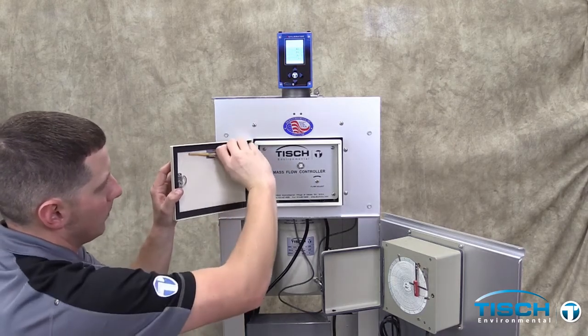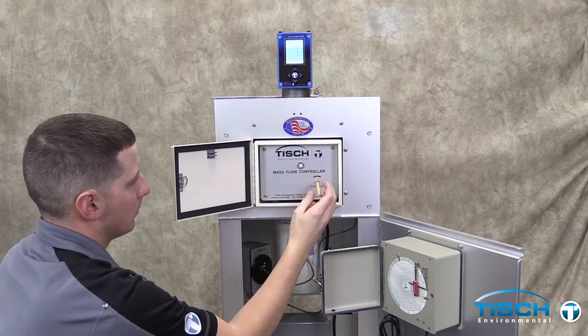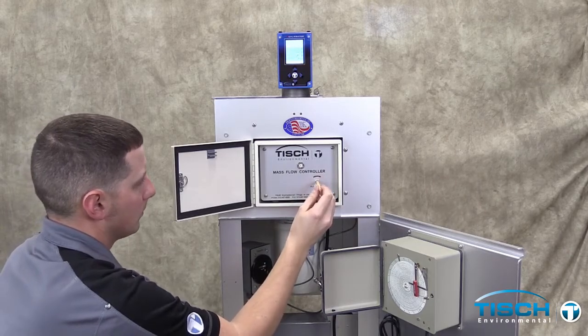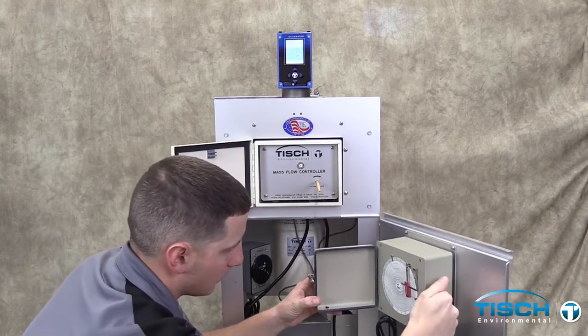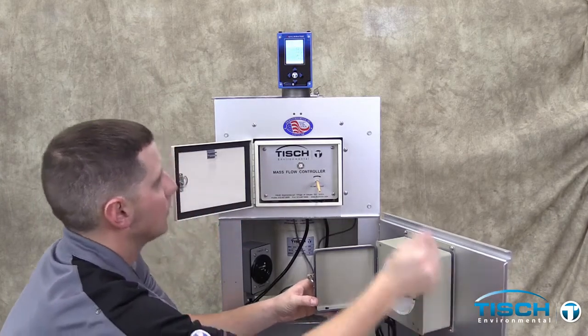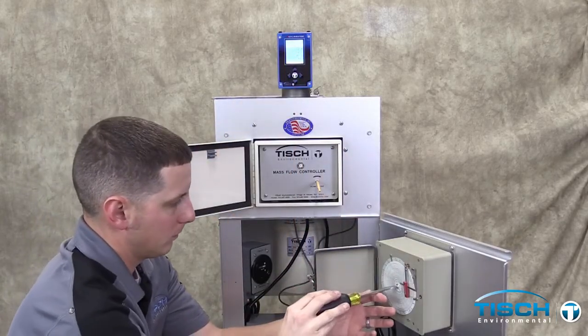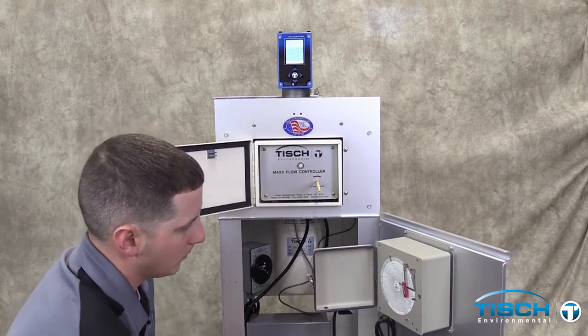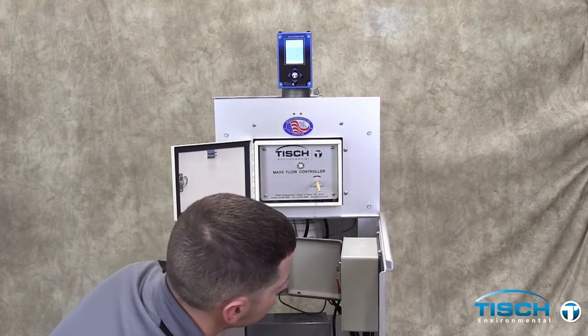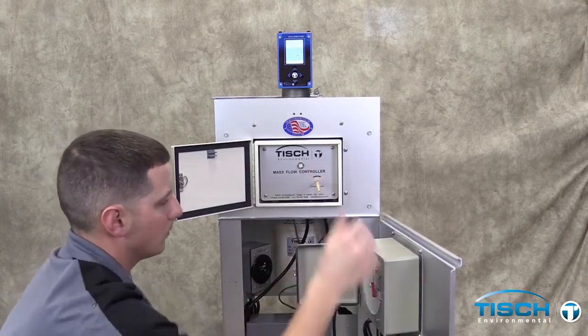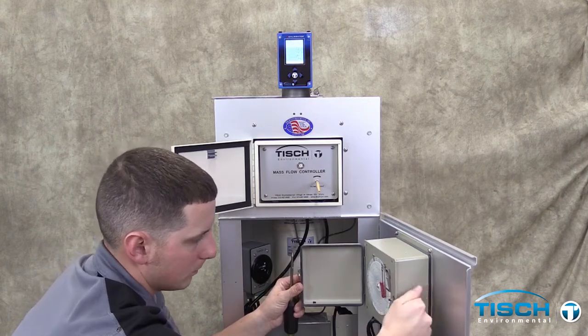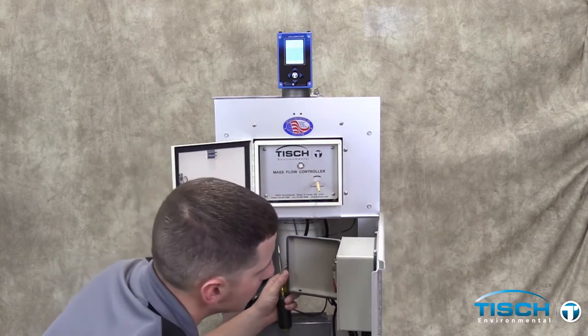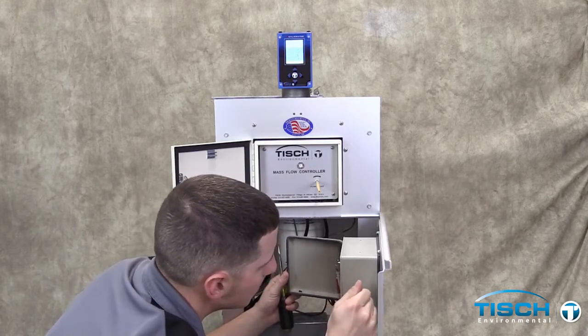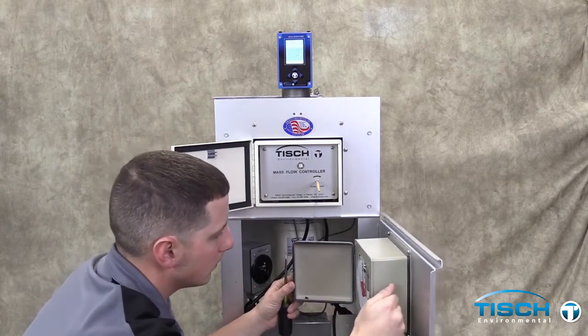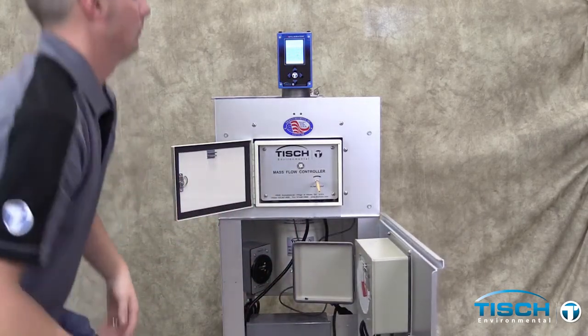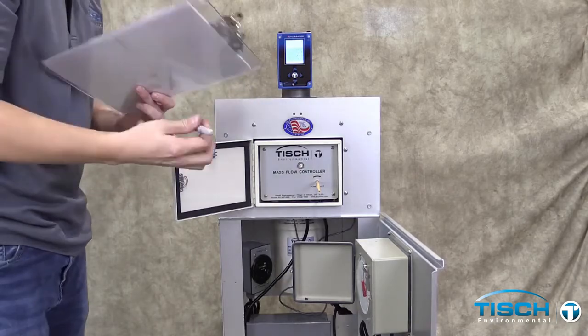After the motor has warmed up, turn the flow on the mass flow controller up by turning the screwdriver clockwise. It is best to have 2 readings above the normal operating flow rate and 2 readings below the normal operating flow rate. Record the recorder chart reading and record the Q ambient reading from the calibrator. Repeat these steps to get 5 different readings.